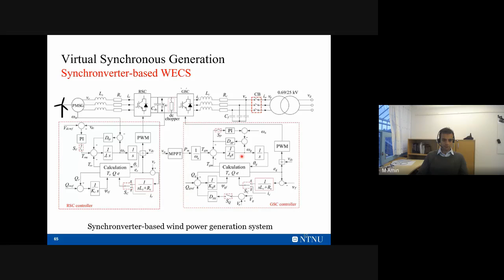But one limitation we noticed is that it doesn't have any internal current controller. So if there is any fault or anything happens, it cannot limit the current. That is one of the disadvantages of this control. Otherwise, this control works and its performance is very good in terms of regulating the voltage and the frequency and minimizing the communication in the system.